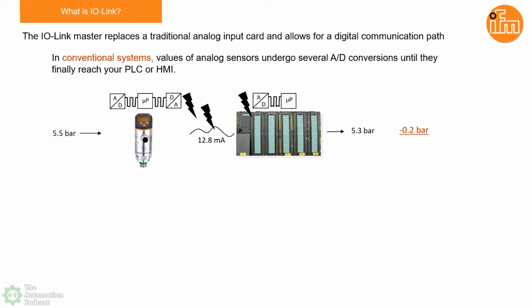First, there's an A/D conversion that converts the analog sensing element into a digital signal in the microprocessor of our sensor. From the microprocessor, we have to reconvert that to an analog signal to bring it out to the real world. Then the analog signal transmits over those 2 or 3 wires back to the PLC, which again needs to convert the analog signal back to a digital signal to process in its microprocessor. Through that entire life cycle, you might lose a bit of accuracy because of all those A/D conversions.